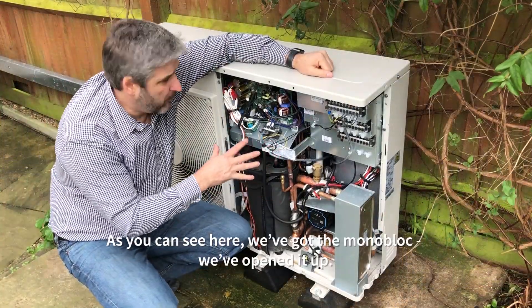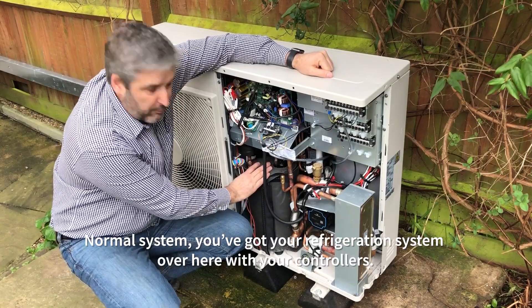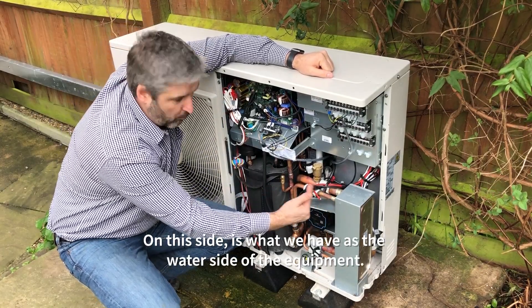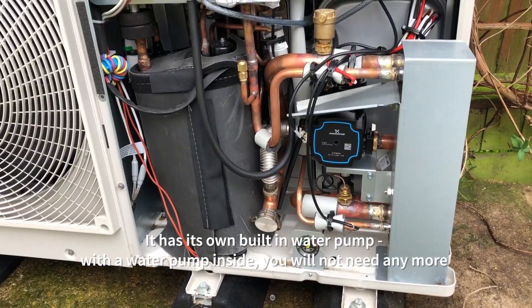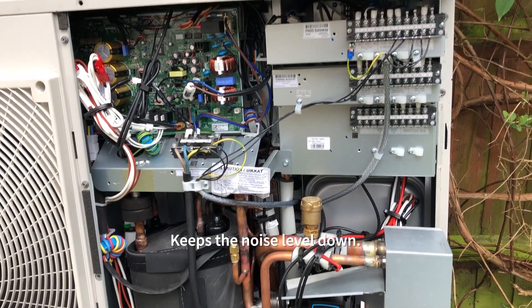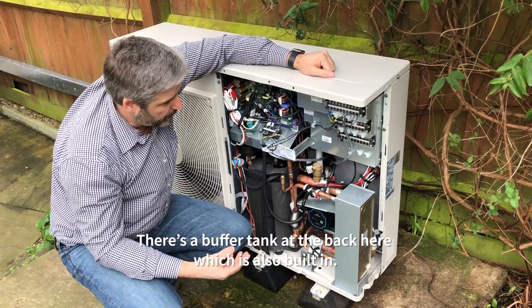As you can see here, we've got the monoblock and we've opened it up. On a normal system you've got your refrigeration system over here with your controllers. On this side is the water side of the equipment. It has its own built-in water pump, so theoretically you will not need any more water pump. It keeps the noise level down. There's a buffer tank at the back here which is also built in.